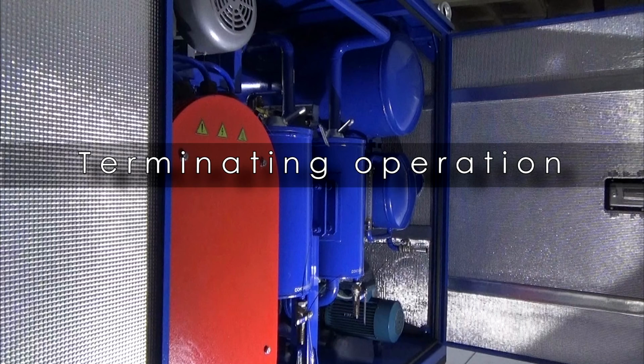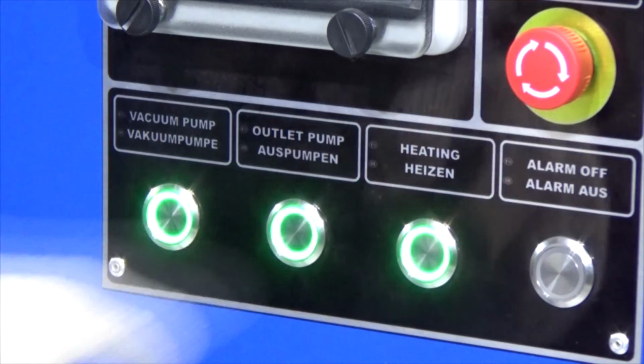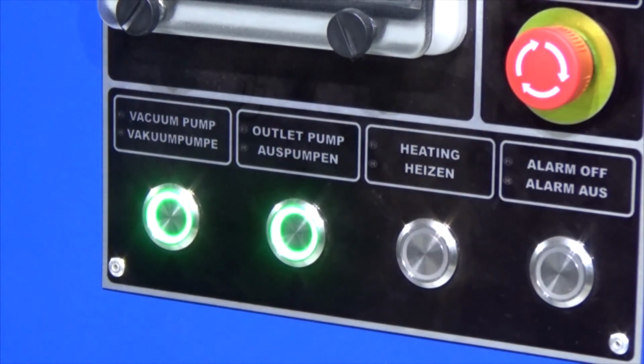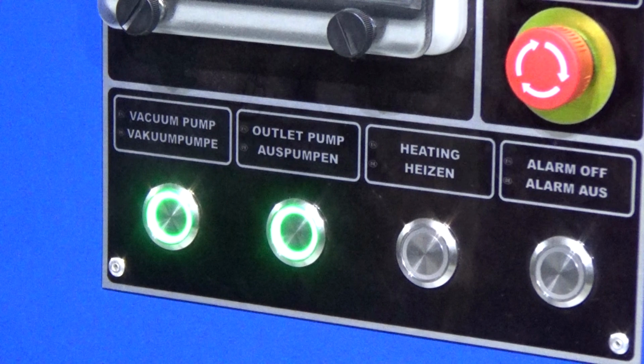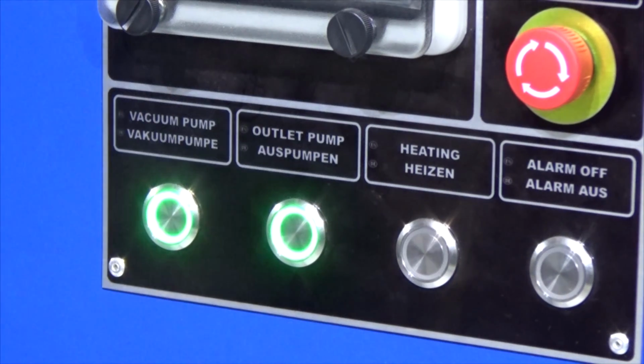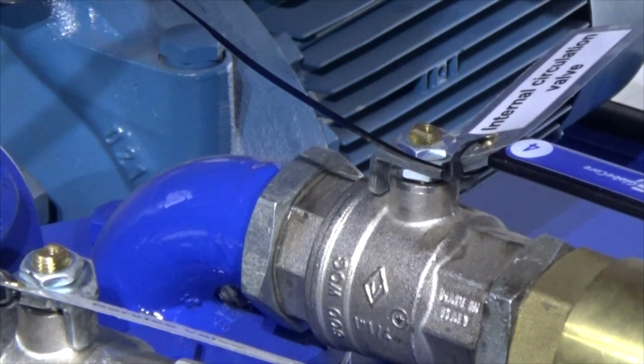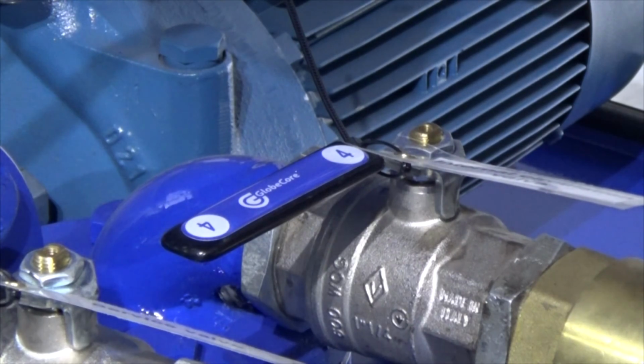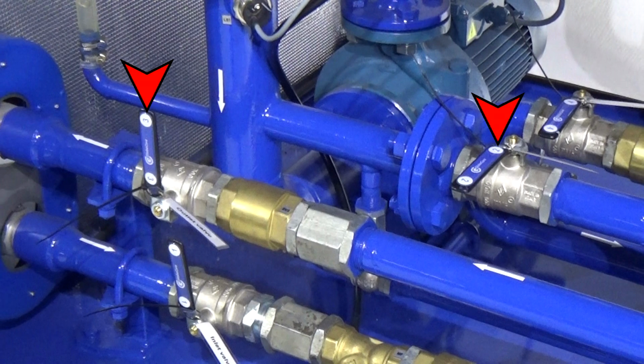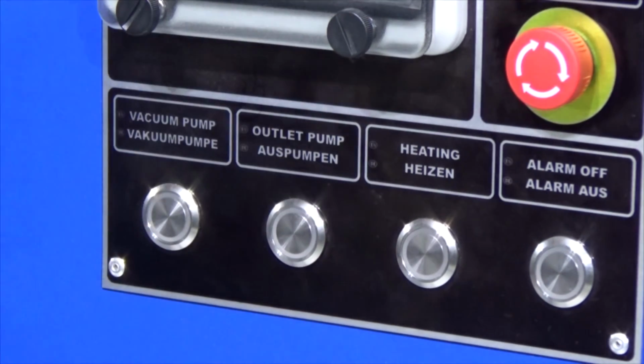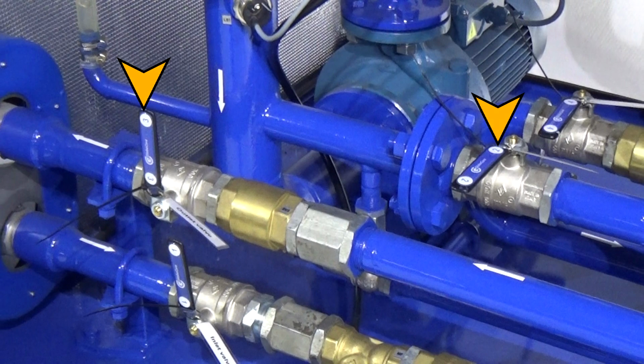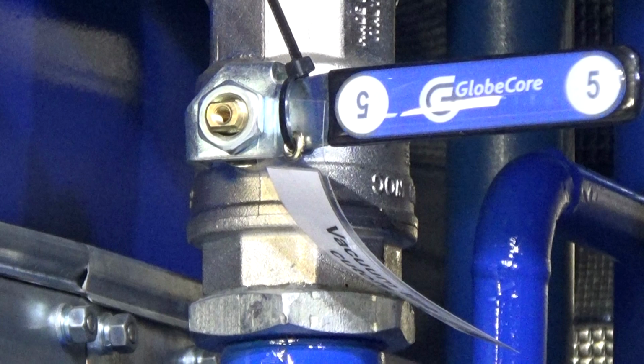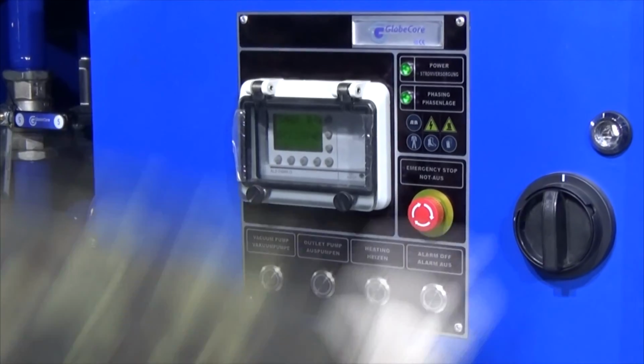Terminating the operation. 1. Disengage the heater by pressing the heating button about 5 to 10 minutes before shutting down of the unit to prevent overheating of oil in the heater chamber. 2. Stop the vacuum pump by pressing the vacuum pump button. 3. Close valve MV4 and open valves MV2 and MV3. 4. After the outlet pump drive stops, disengage the pump by pressing the outlet pump button. 5. Close valves MV2, MV3, and MV5. 6. Turn the power handle to the off position.